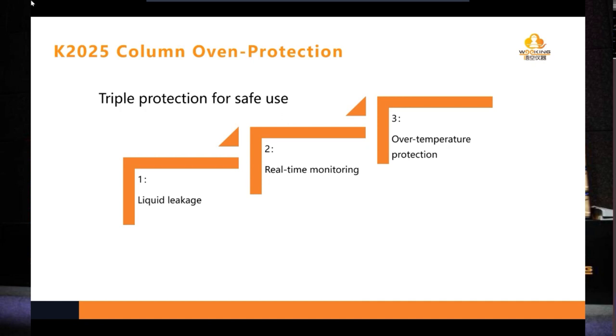Next, there are 3 protections for safer use of the column oven. The first one is the liquid leak sensor. The liquid leak sensor in the column oven is not the same one used for the other units. And the second is real-time monitoring of temperature. And third is over temperature protection. When the temperature reaches certain values, the oven will shut down to ensure the safety of users and the hardware.